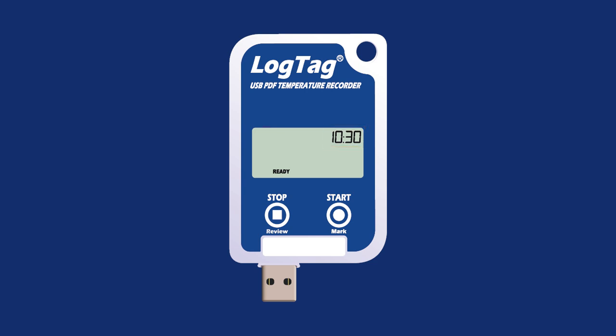If the logger is pre-configured to start when the Start Mark button is pressed, Ready will display on the screen. If DTST displays, the logger has been pre-configured for a specific date and time start. Finally, if the logger is pre-configured for a pushbutton start with a Start Delay, the word Delay will display along with how long this delay time will be.